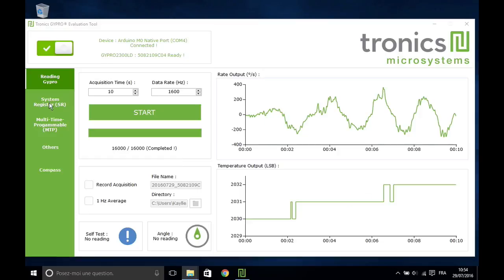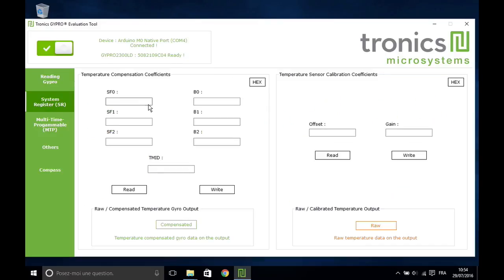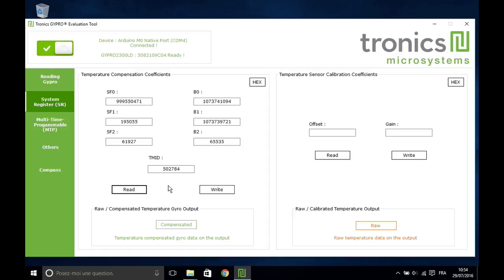Now move to the System Register tab. The left box shows the temperature compensation coefficients for the angular rate output. You can read the coefficients that have been programmed by Tronics inside the sensor or write temporarily some new values.